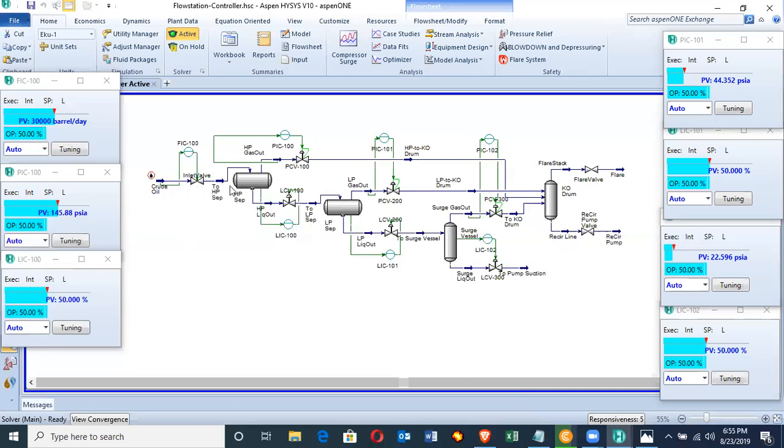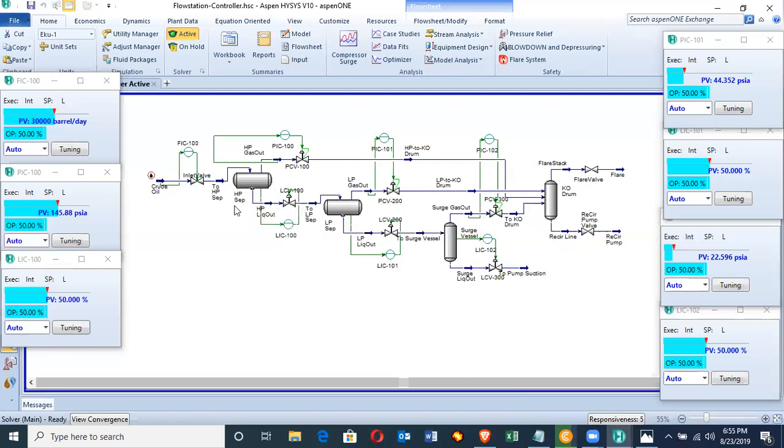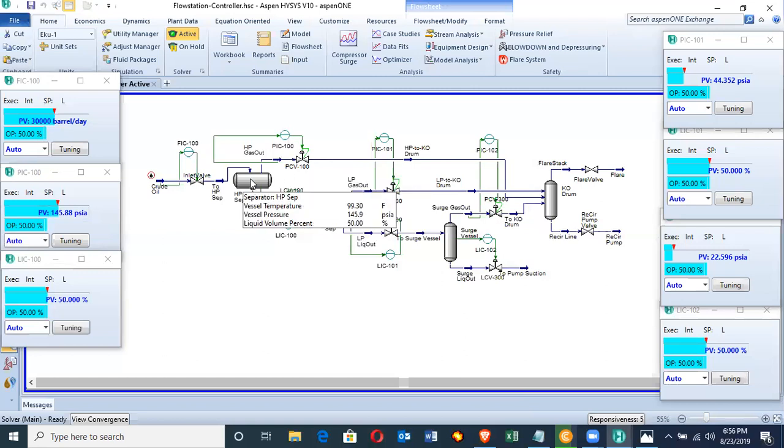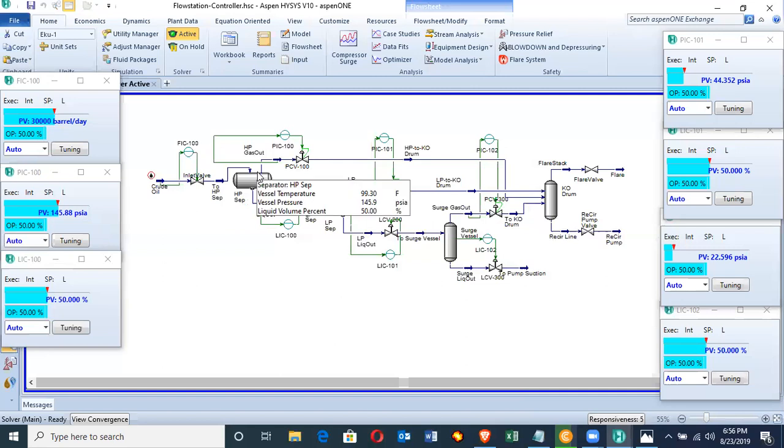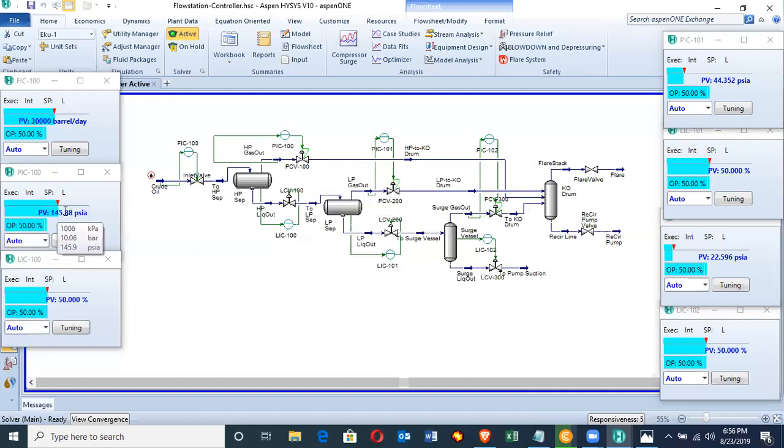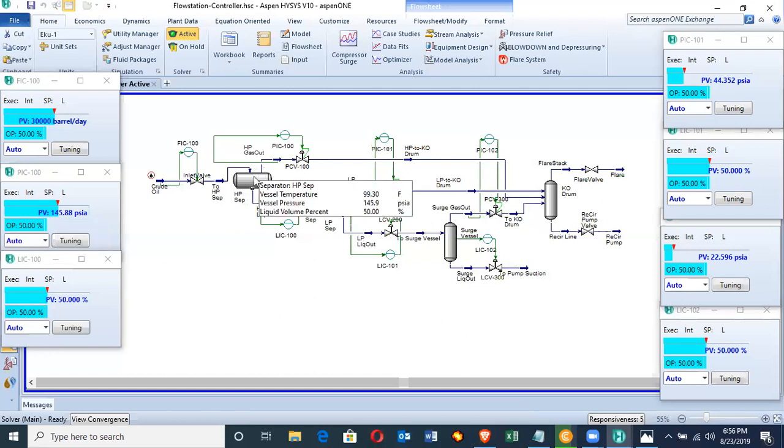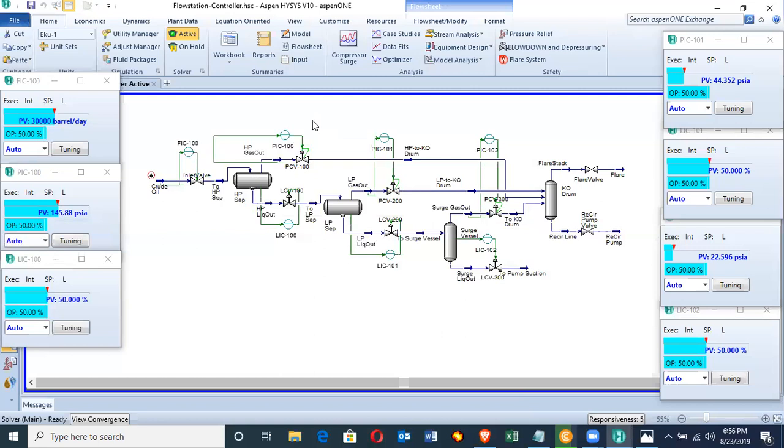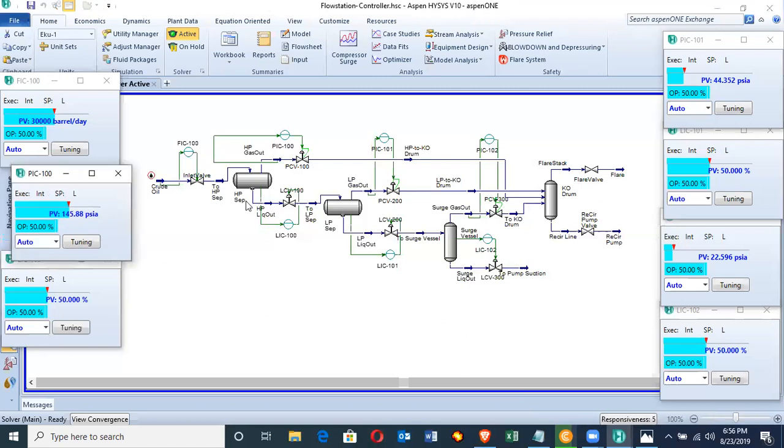For the HP separator, the HP operates at 145.8 PSI. This is the set pressure for this HP. If the pressure within this HP separator is above or below the set pressure, the pressure indicator controller measures that pressure, compares it with the set pressure, and sends the proper signal to trigger the pressure control valve to either open above 50% or below 50%.